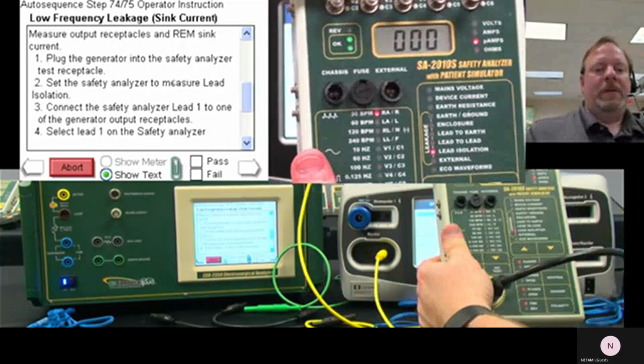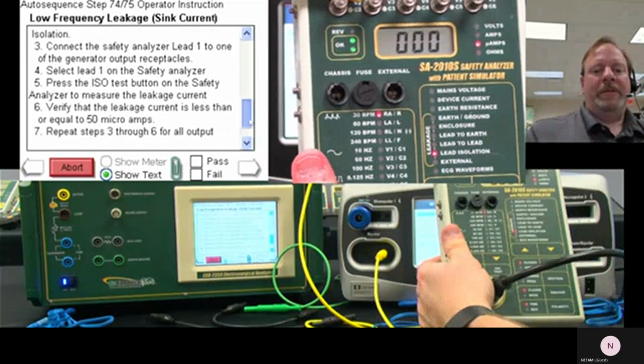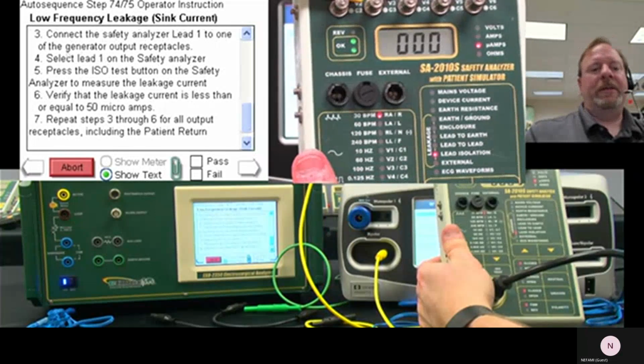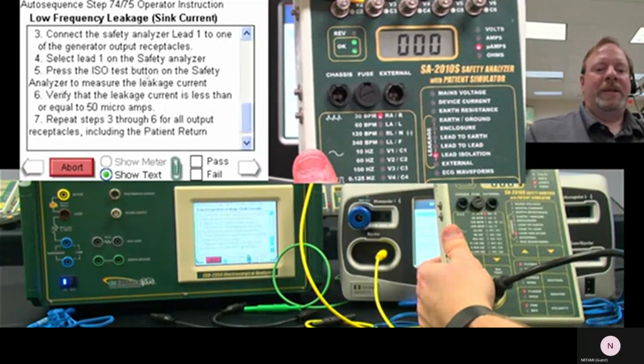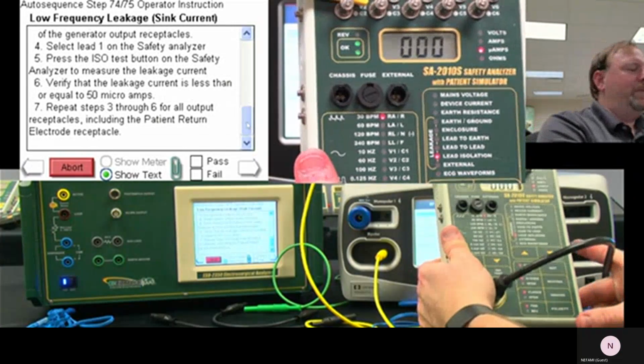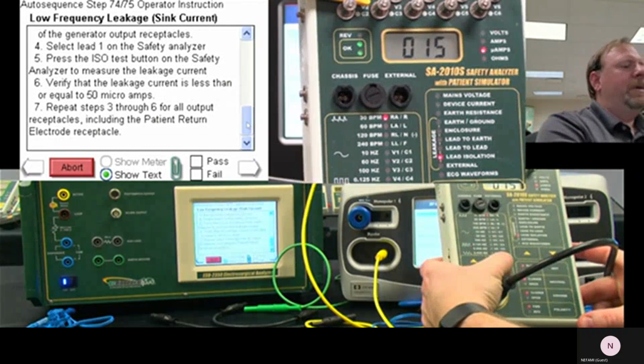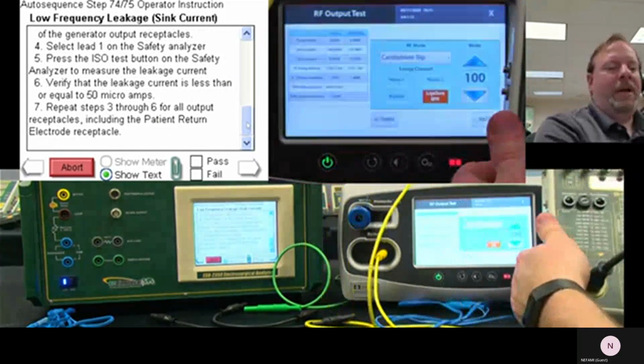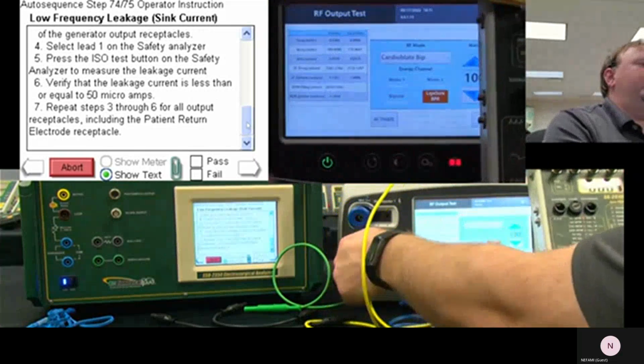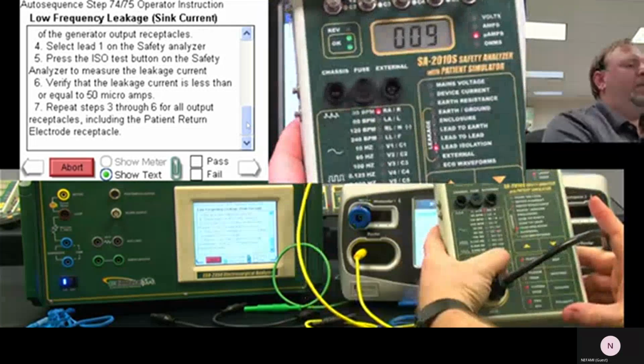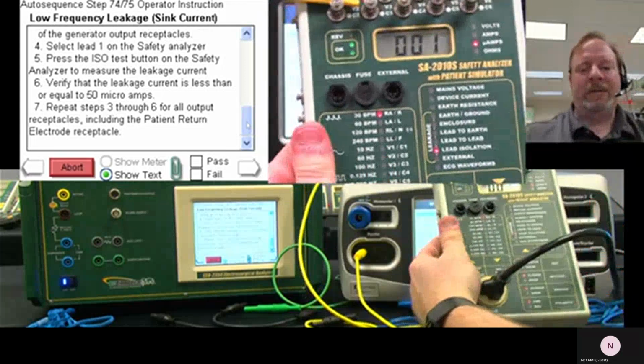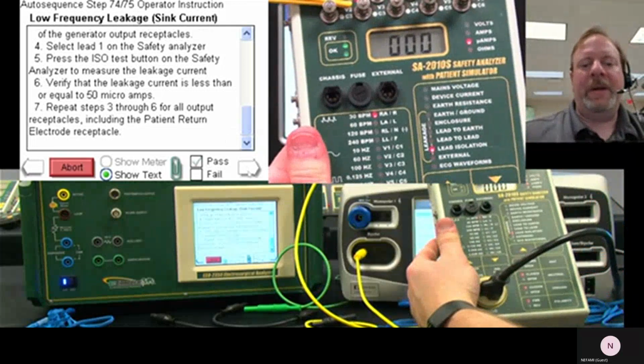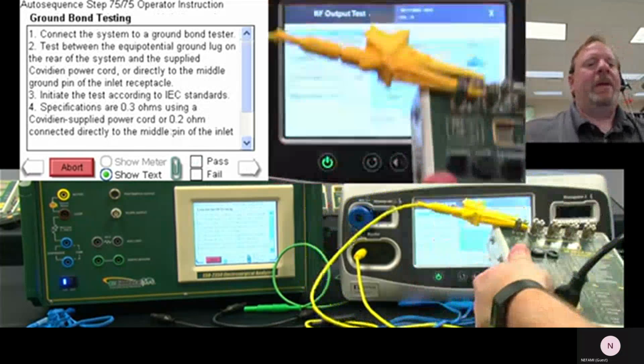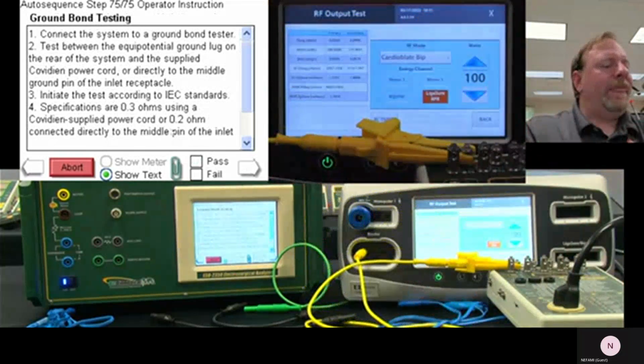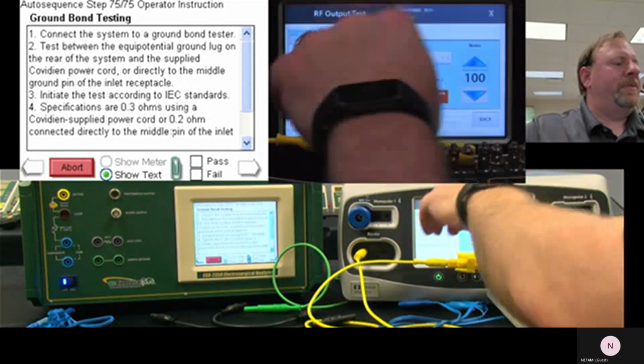So follow the instructions here. I didn't show all the instructions. Connect to lead 1, select lead 1, press ISO test, verify the leakage current is less than 50 microamps. So we are. And then it says repeat for all output receptacles, every single one. Check them all. We'll pretend like we checked them all, and they are all under 50 microamps. It is safe.